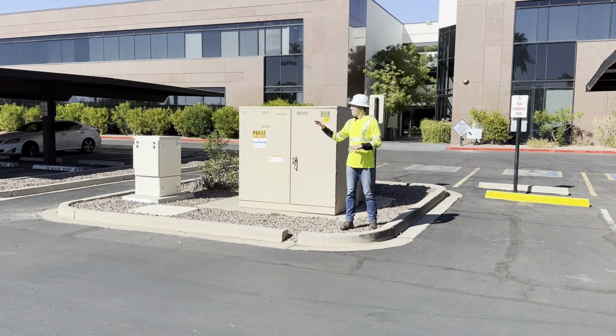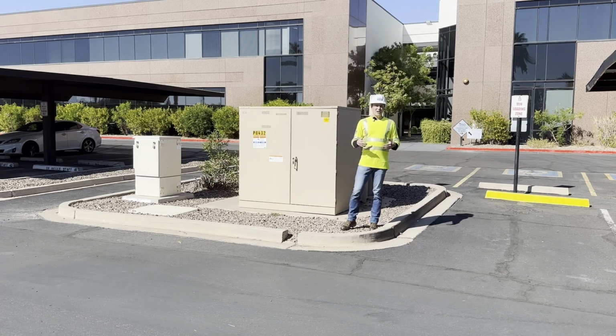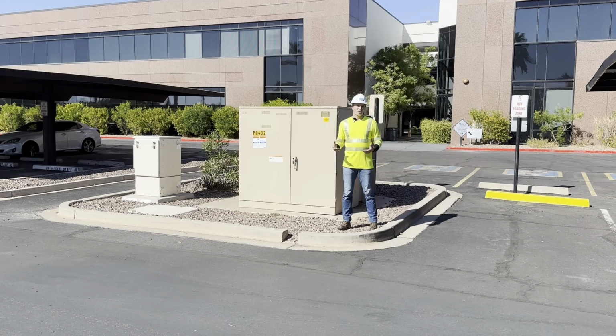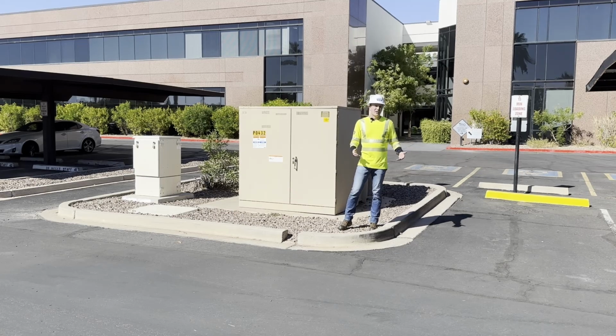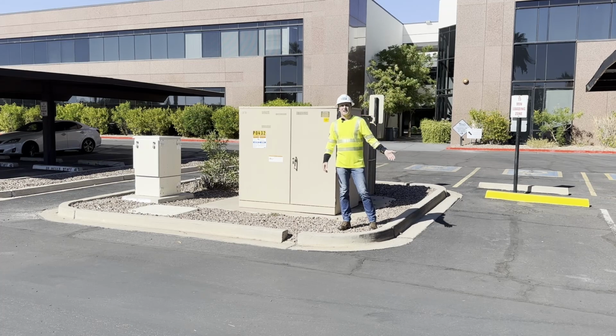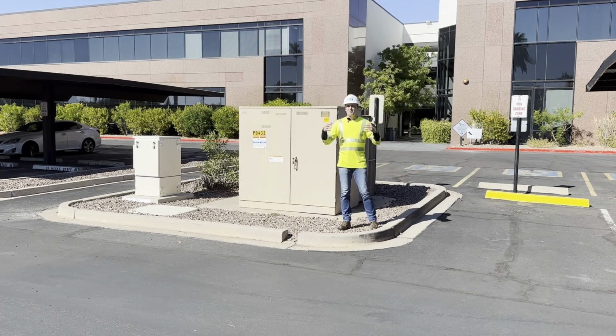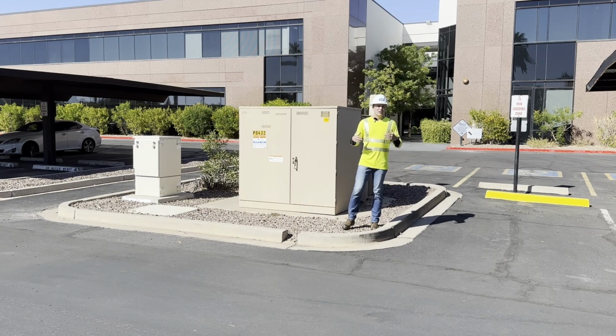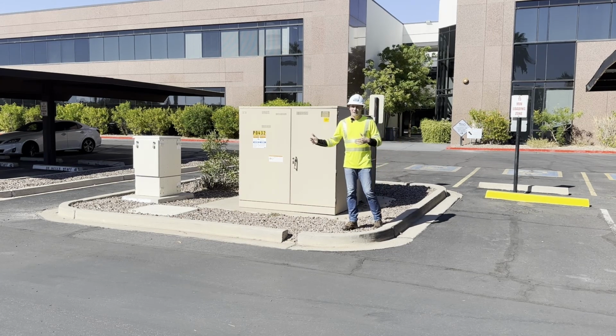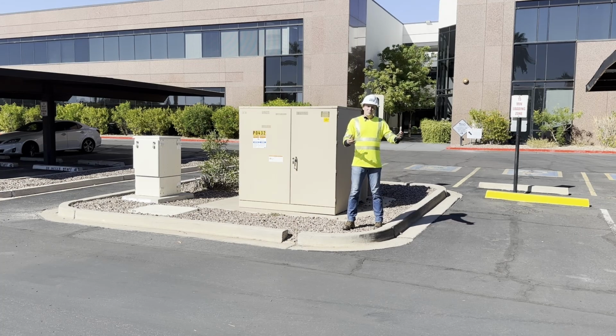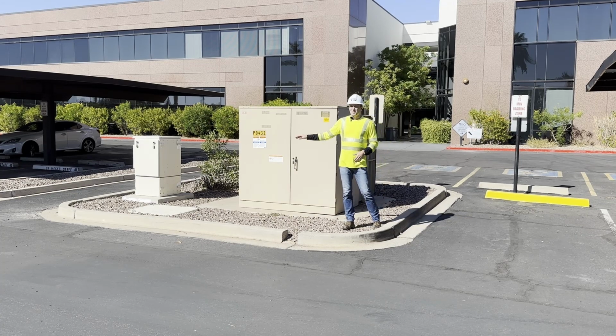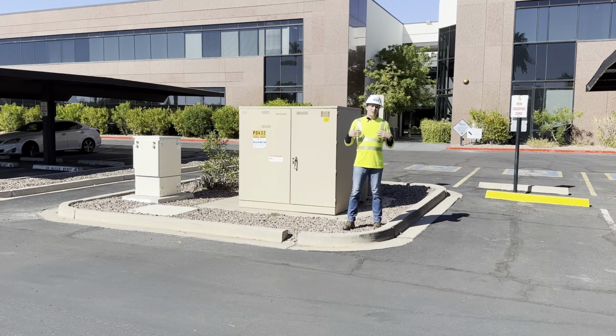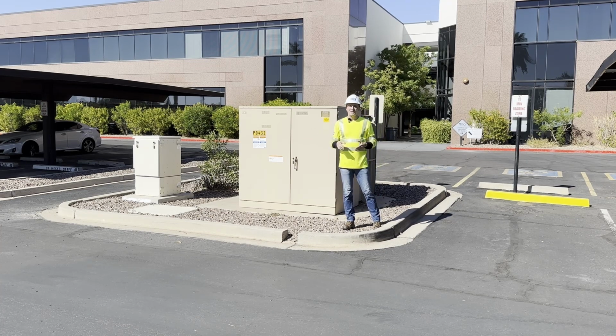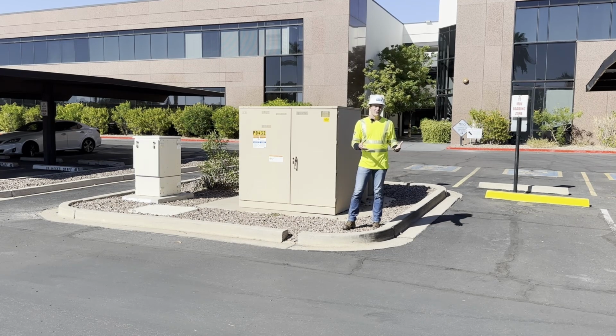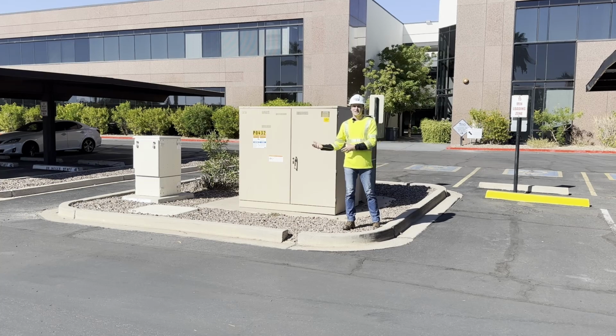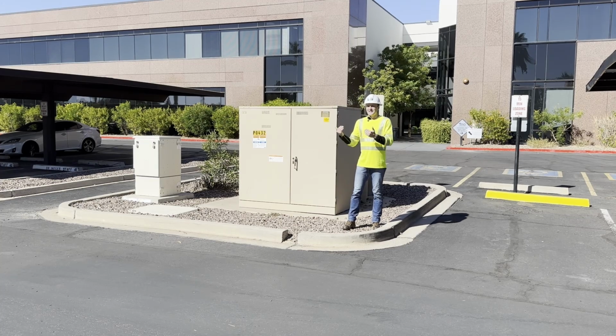secondary services. But some electric utilities throughout the country will actually have larger 277/480 volt transformers, such as Southern California Edison, which has one that goes up to 3325 kVA, and Pacific Gas and Electric, which is 3750 kVA. So those are big, juicy transformers that are great for EV charging projects, because then you can get a higher load to that. But these sizes are super important, and really that size is determined by the utility, not as much the customer. We give them the load for our EV charging projects, and they go behind the scenes, do their own diversification calculations, and then come back and tell us what they're going to size their transformer to serve our load. It's not always one-to-one.